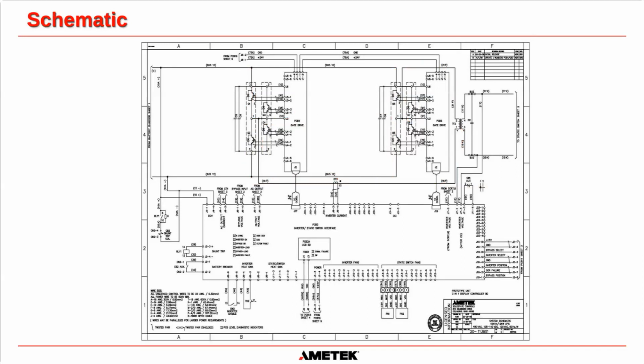Now, similar to the DSE system, when we need a higher powered system, we can put two IGBTs in parallel. So remember, we had A. Let's make this one A, and let's make these ones A, and then let's make these ones B, and these ones B. Instead of having one IGBT, we've now got two IGBTs connected in parallel. It's just to give us a higher current capacity on the output of the system. The gate drive circuit is sending exactly the same signal to both IGBTs, so they both turn on at exactly the same time, and they both turn off at exactly the same time.